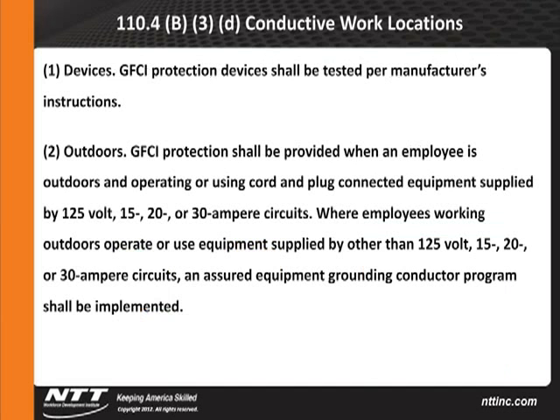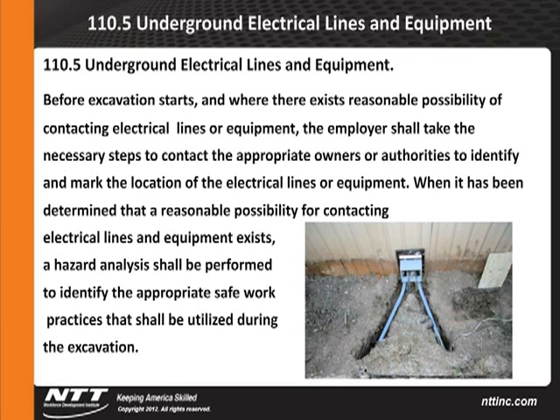Devices. This is the language that's more specific. GFCI protective devices shall be tested per the manufacturer's instructions, and when it's outdoors, it says GFCI protection shall be provided when an employee is outdoors and operating or using cord and plug connected equipment supplied by 125 volt, 15, 20, or 30 amp receptacles. Where employees working outdoors operate or use equipment supplied by other than 125 volts, an assured equipment grounding program shall be implemented. If you're not familiar with that, it means all your cords, all your tools have to be checked for polarity, continuity, tagged, and a record kept before they're ever used, and pulled back out of service every 90 days and redone again and over and over.